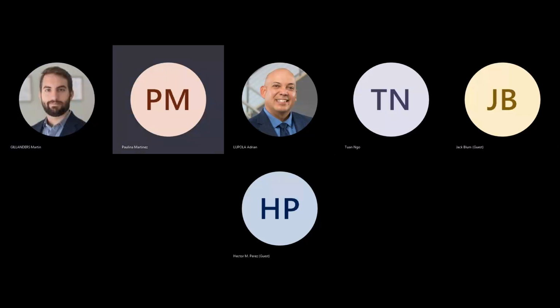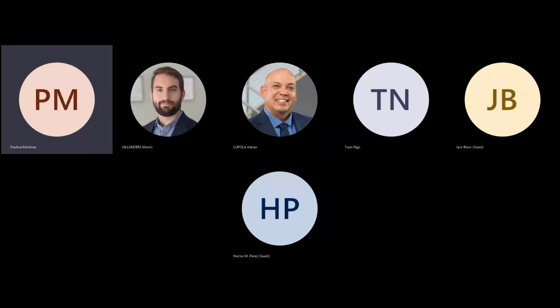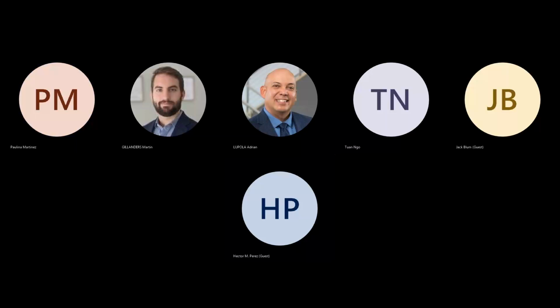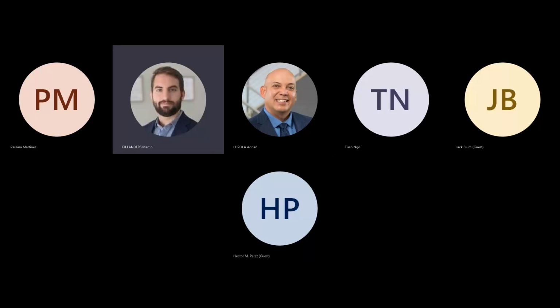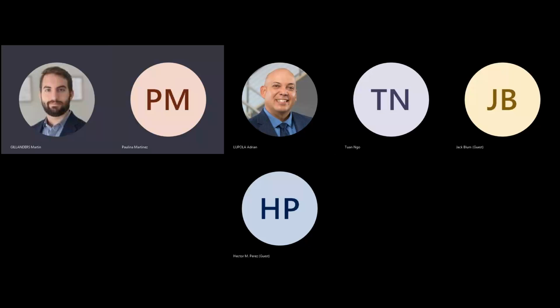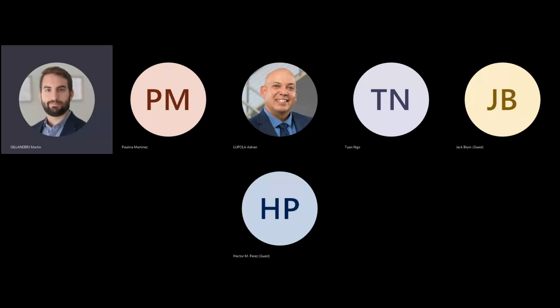Okay. Well, my concern is how would we incorporate that whole system to our older ones? Yeah, so migration is basically what you're asking. Yes. And it really depends on what you're migrating from and to. If you're migrating from RS-View 32, Rockwell internally has migration plans that they can help you move those HMI screens from RS-View 32 into View SE.